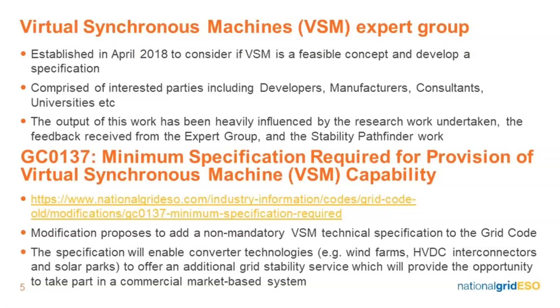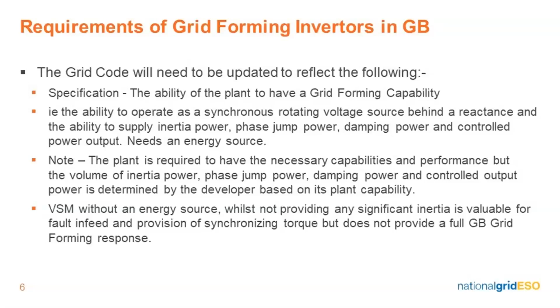This specification talks about the plant's ability to have grid forming capability, i.e. the ability to operate as a synchronous rotating voltage source, and to supply inertia power, phase jump power, damping power, and controlled power output. But it does need an energy source, I must stress this. The VSM without an energy source doesn't really provide inertia, though it's valuable for fault in-feed and provision of synchronizing torque. But from our perspective, it doesn't provide the full grid forming response we need to operate a secure system.